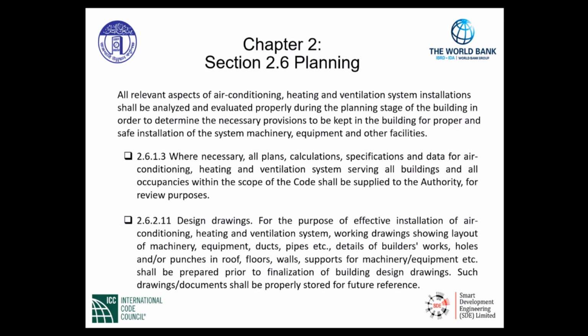Section 2.6.2.11, Design Drawings. For the purpose of effective installation of air conditioning, heating, and ventilation systems, working drawings showing layout of machinery, equipment, ducts, pipes, etc., details of builder's works, holes and/or punches in roof, floors, walls, supports for machinery, equipment, etc., shall be prepared prior to finalization of building design drawings. Such drawings or documents shall be properly stored for future reference. Again, giving specific installation and layout drawings and routing drawings of the equipment and systems specifically is a requirement in this section.